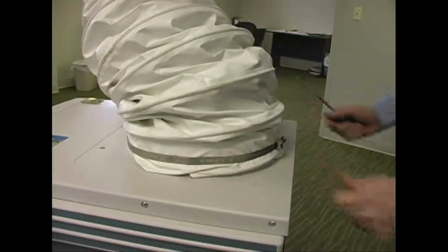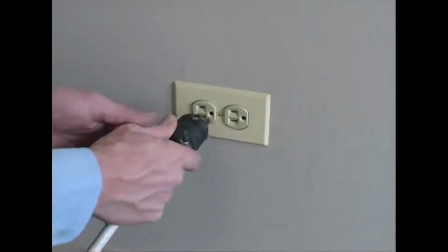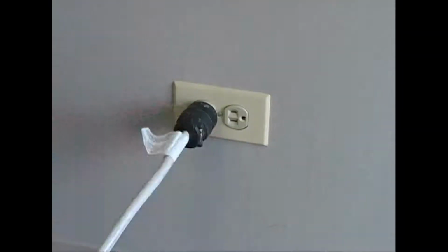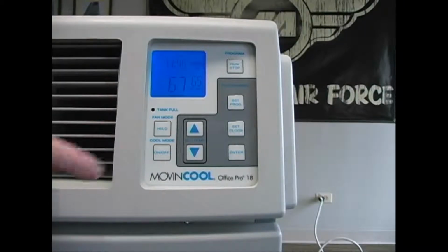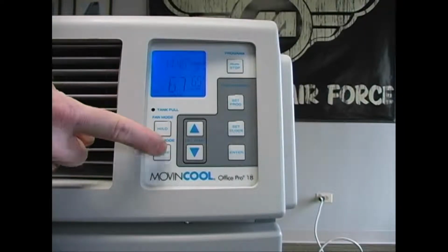However, these options to vent condenser air are not always available, and without being properly vented, an air-cooled unit can make a bad situation worse. An example of this would be a server room that is not configured to handle the vented air from a portable cooling unit. It's a common mistake that leads to more problems. The hot air from the condenser side builds up in an area above the drop ceiling and ultimately leaks back into the server room, causing even higher temperatures.